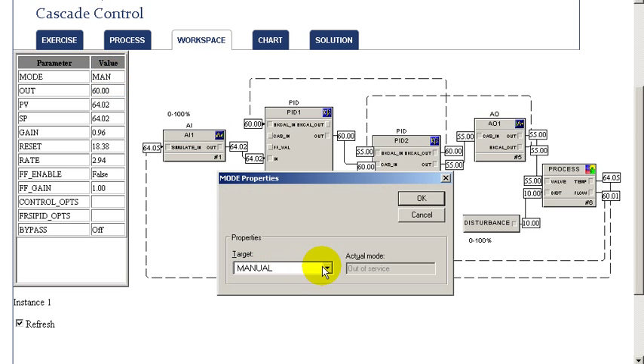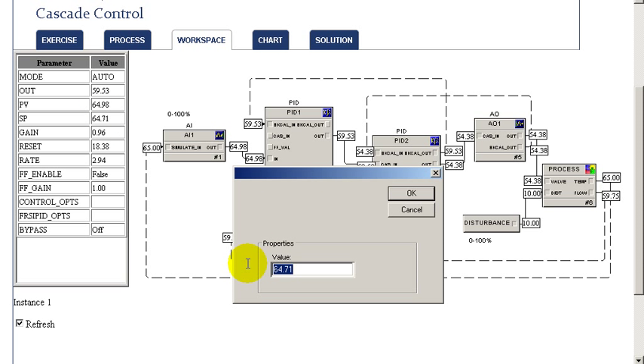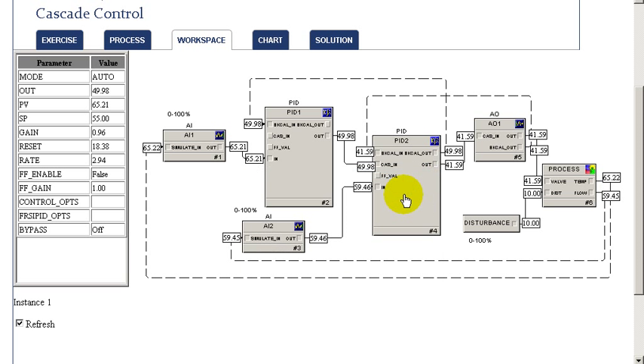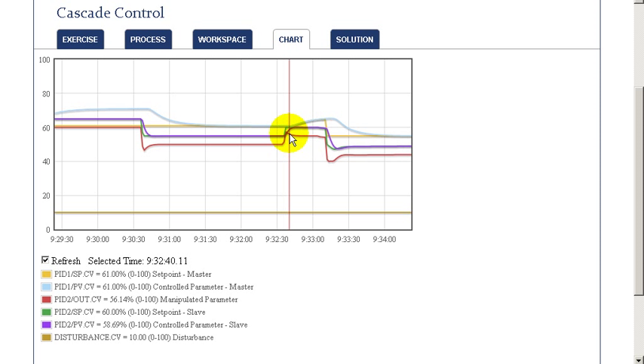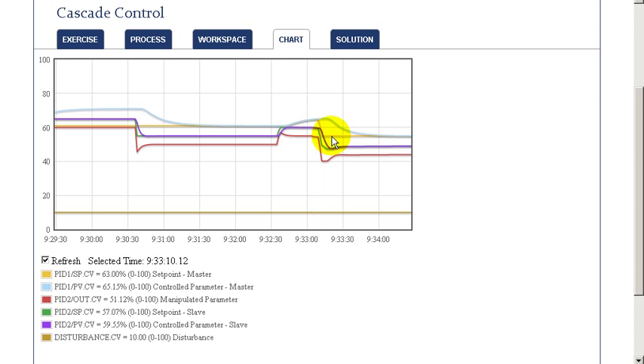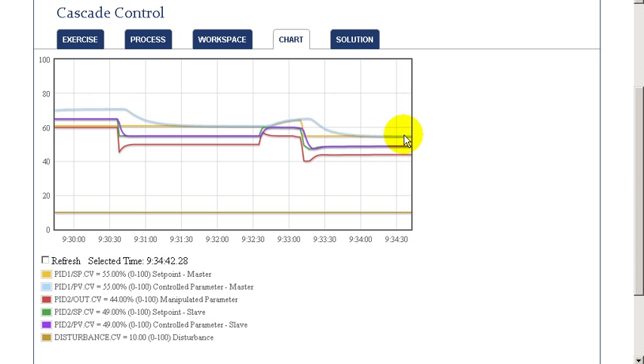By putting the master loop into automatic mode, we can examine the behavior of the loop when we change the setpoint. When we change the setpoint of our master loop, its change in output impacts the setpoint of our slave. The slave then adjusts its output to achieve its new setpoint value, which in turn drives the master loop to its setpoint. This can be seen in our chart — the setpoint of our slave loop was changed by the master loop to bring it to setpoint, and so these work together to achieve the setpoint of the master loop.